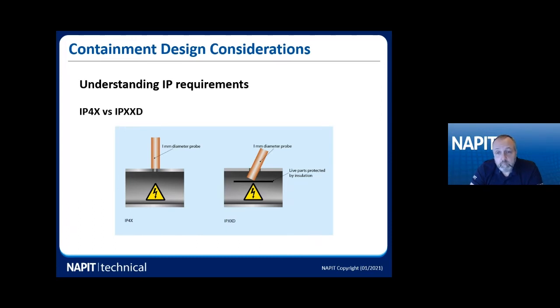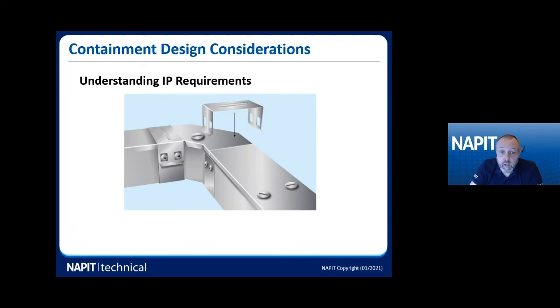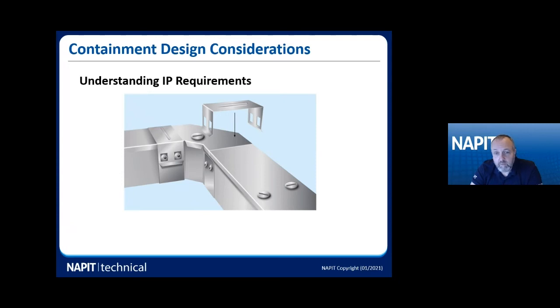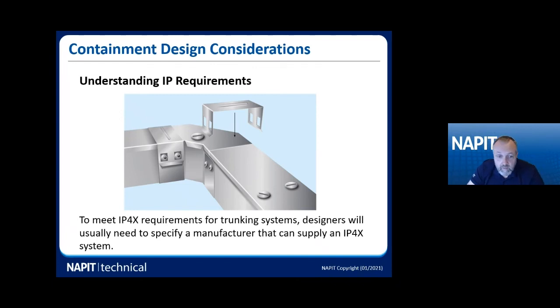When specifying trunking, you need to make sure the particular manufacturer can provide an IP4X rated trunking and lid system. You need to be very careful, and if you're going to do any site-made cuts or joints, it's unlikely you can then achieve an IP4X solution — because no matter how accurate you are, you'll always get a bit of a gap. However, provided you can meet IPxxD, site-made cuts can generally be acceptable.